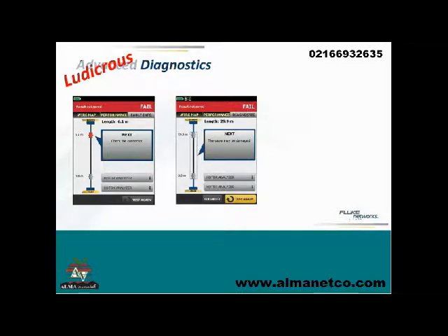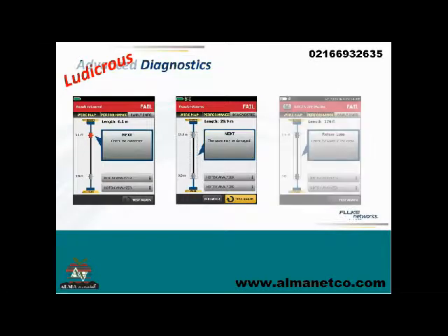Another one is that it can tell if the cable's damaged or if the cable's actually bad quality. I mentioned the copper-clad aluminum and all that. It'll tell you exactly which cable and where in the cable. And in this case it says it's not a spot in the cable, it's the whole cable that has a problem. A lot of this is because we've worked with tens of thousands of customers who've had problems, and we now know what they look like electronically, so we can put it into this simple display. But this is my favorite: we can actually tell if there's water in the cable, because we know now what that looks like.